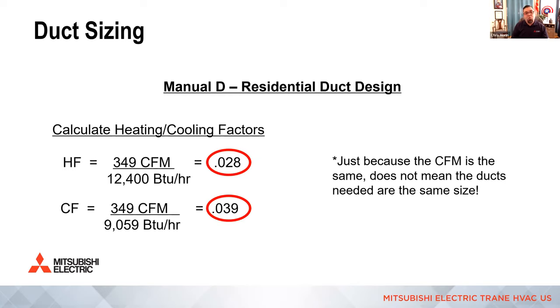Then of course, we're going to divide that by the heat loss for those zone or room. In this example, it was only 12,400. That would come off of my Manual J report. And you only want to go three decimal points. Anything past three decimal points will not change the duct run size. So in this example, the heating factor, when you do that math, is 0.028. Of course, you do the same thing with just the sensible gain in cooling. Volume of air divided by, in this example, 9,059 gives me 0.039 as the cooling factor.